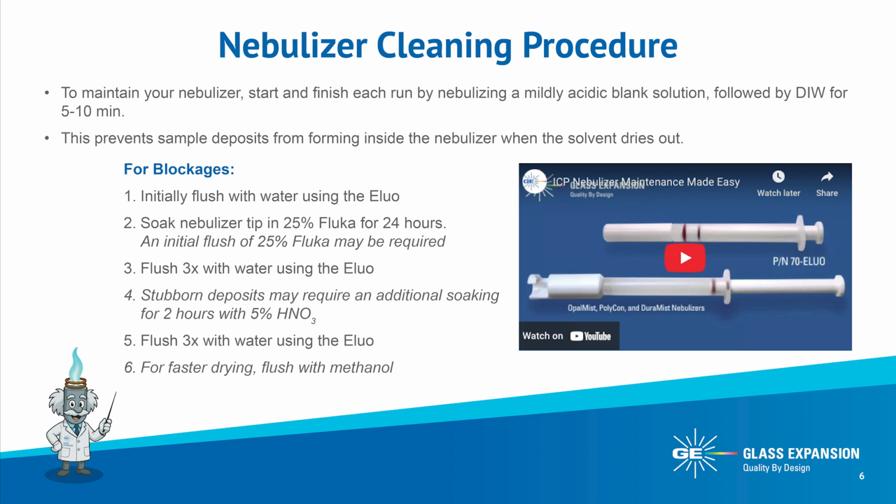And here's a tip to improve nebulizer maintenance schedules. Start and end each analysis by running a mildly acidic blank solution, followed by deionized water, each for 5 to 10 minutes. This will prevent deposits from building up in the capillary tubing or nebulizer orifice.